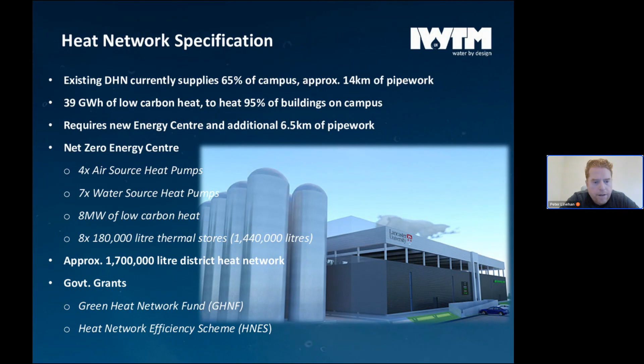That requires a new net zero energy center. Within that energy center, you have 4 air source heat pumps and 7 water source heat pumps producing 8 megawatts of low carbon heat. With any type of heat pump, you need a lot of storage, and they have 8 180,000 litre thermal stores, which amounts to 1.44 million litres of water. So with this district heating system, we're talking huge, vast amounts of water that need to be treated and prevented from causing corrosion. They did receive grants, just to touch on it, from the Green Heat Network Fund and the Heat Network Efficiency Scheme.